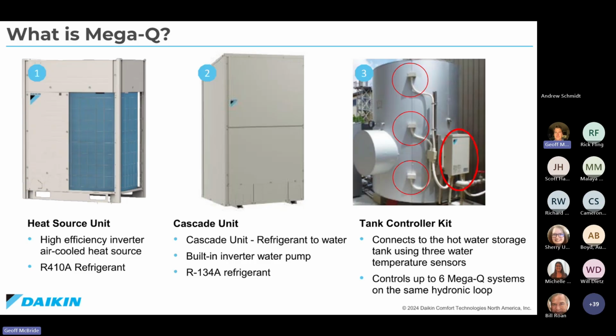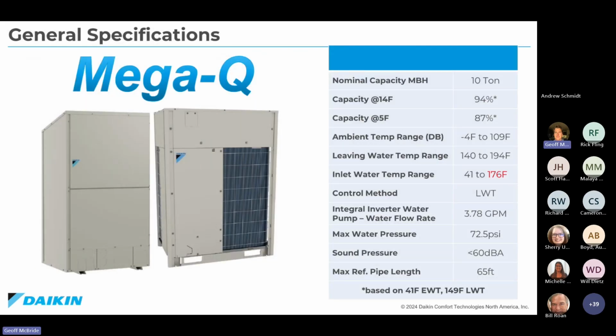a tank. The tank will be a third-party tank, so there'll be a lot of different options. The cool thing with this system is you can pair up to 6 MegaQ systems, up to 10-ton each. So basically 60 tons, with 6 cascade units and 6 10-ton air source heat pumps to make a 60-ton MegaQ system. So you can generate quite a lot of hot water with this. You see just some of the specs over here on the right. Ambient temperature outside, it will operate down to -4. So it's obviously something to consider because we do get colder than that in terms of what you do with the tank. Maybe you have to add electric heater backup to it. But we can get to some pretty warm temperatures, some hot temperatures with this solution.